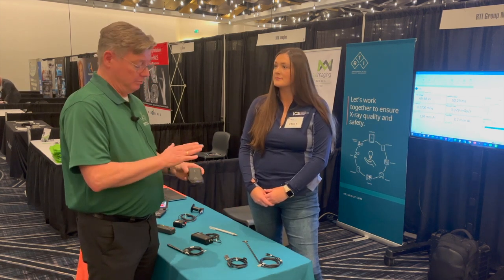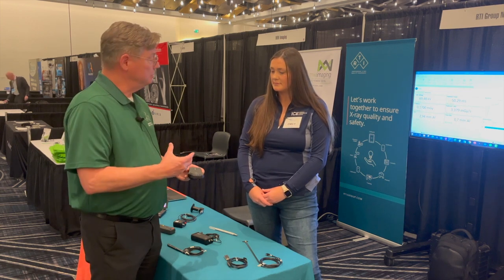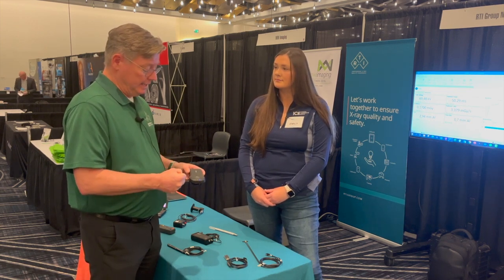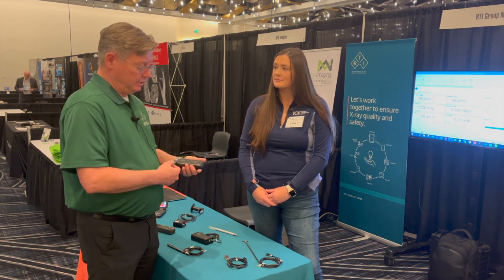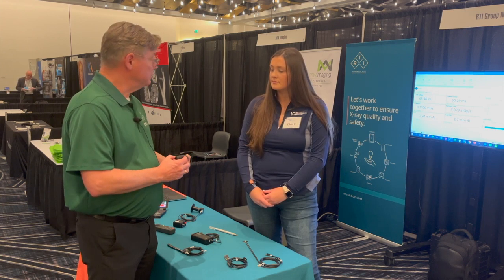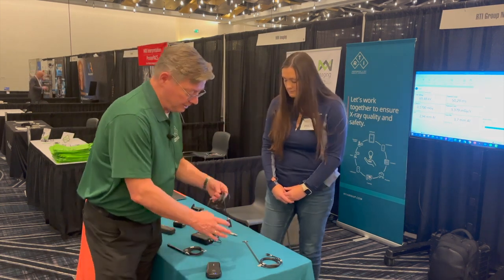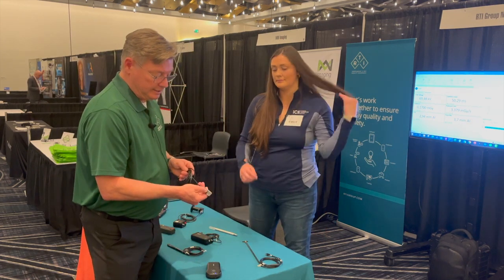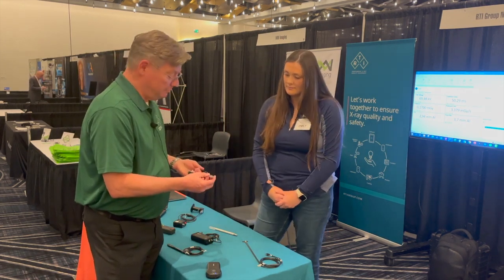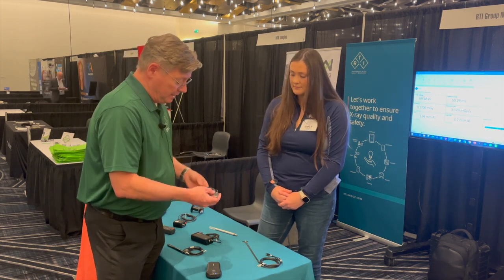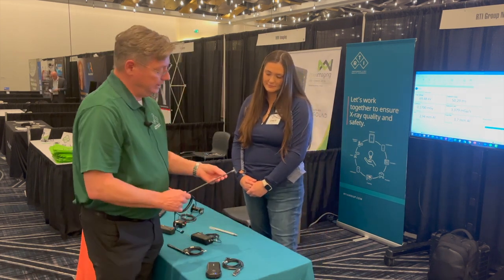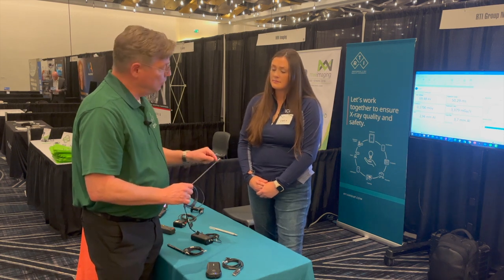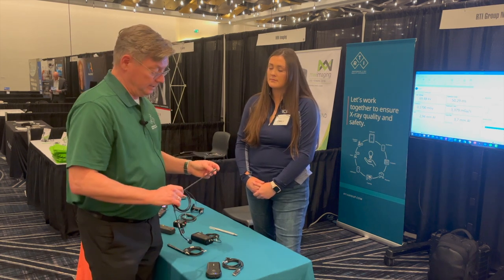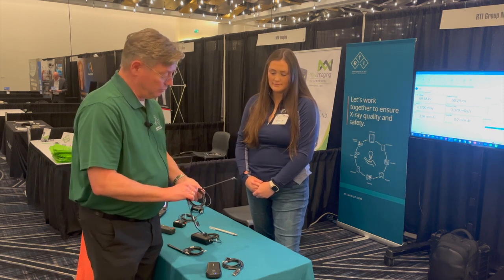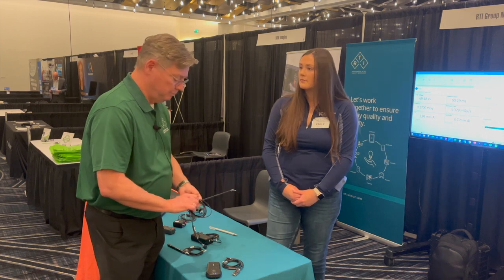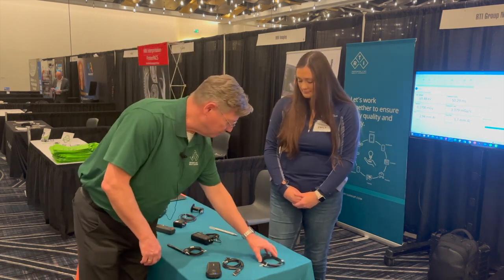This is the base unit. So we put this in the X-ray beam, and we pick up the KV, the dose, total filtration, and all that. For certain applications, we have an extra port right there, which connects different probes. So we have a collection of probes. We have an external dose probe, looks like this. It's 10 by 10 square millimeters, so it's also quite sensitive, 100 square millimeters. We have a smaller one, which is useful in fluoro situations, where you have a small footprint to measure the dose, so you don't affect the AEC too much. There's a carbon fiber rod to allow it to move it around and position it in a good position. So that's quite popular as well.